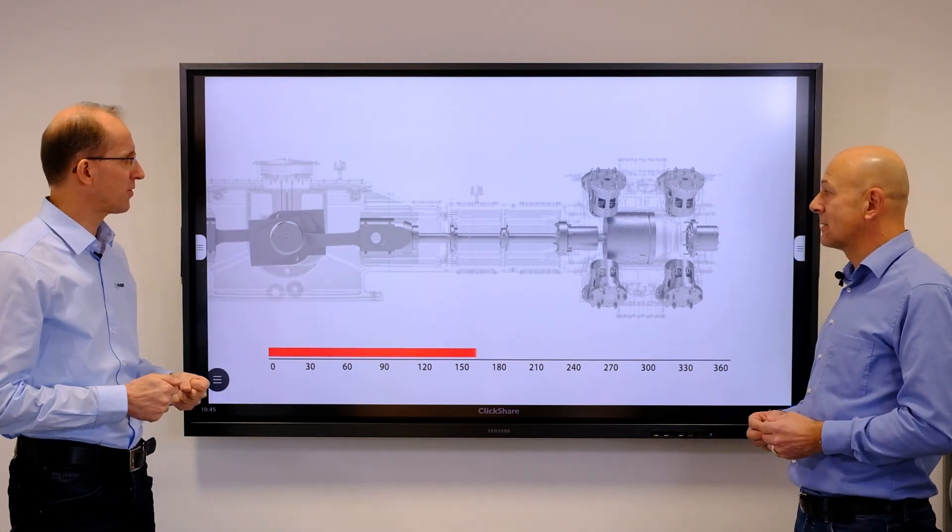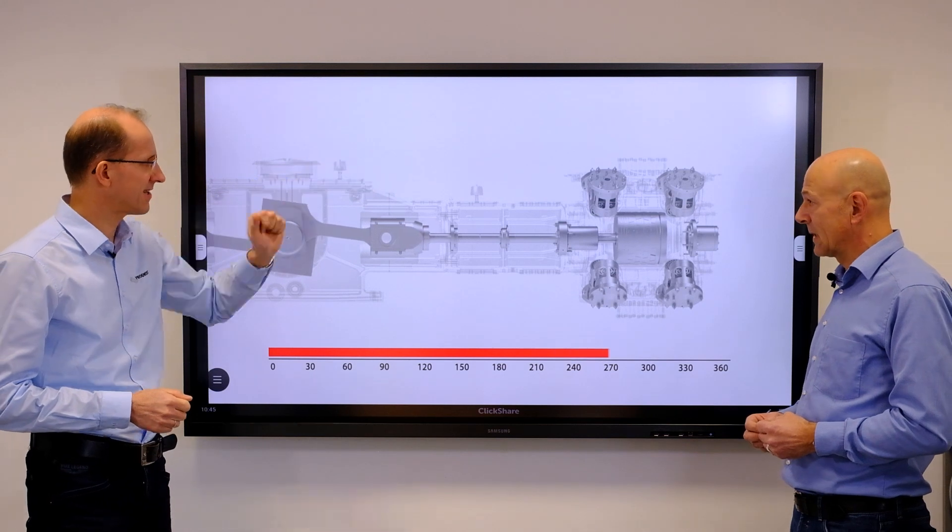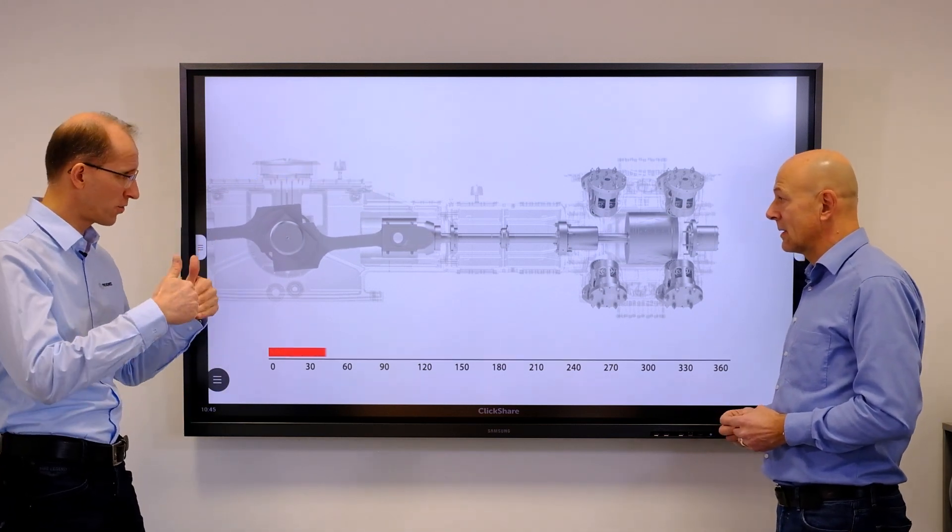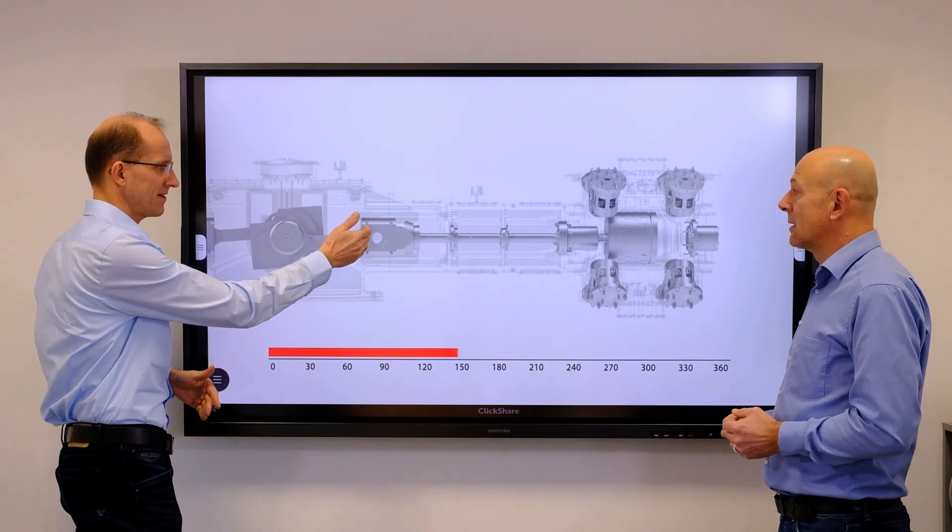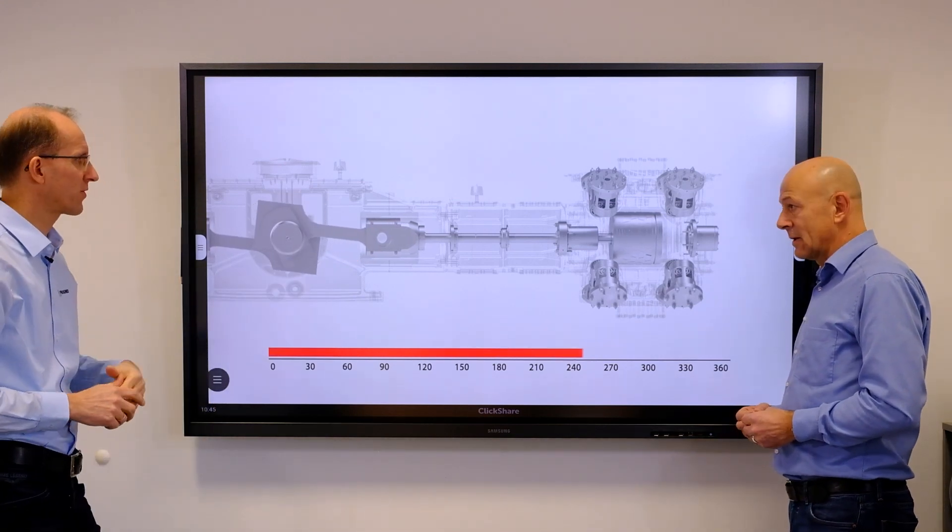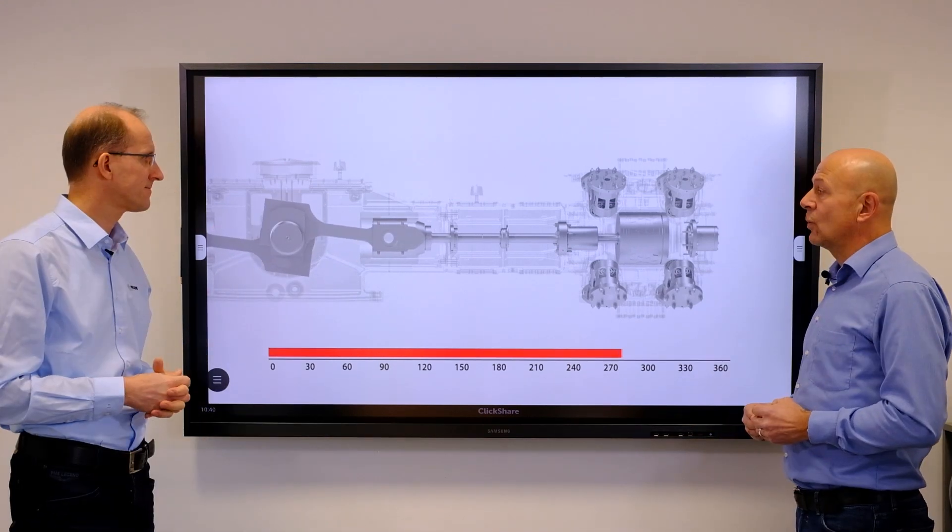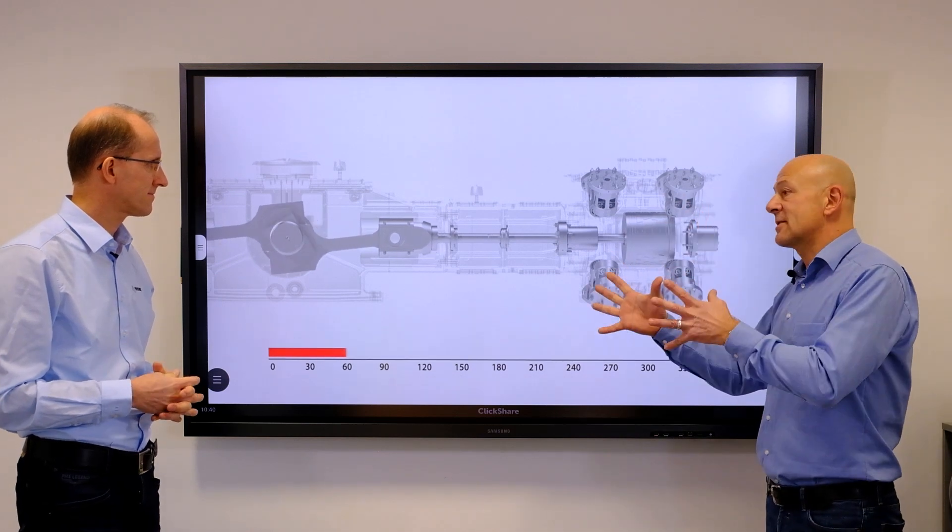What we have seen from a couple of cases is that the crosshead slide vibration sensor picks this up early, and even earlier than the temperature monitoring of the crosshead wrist pin. And we can demonstrate that in a case study.